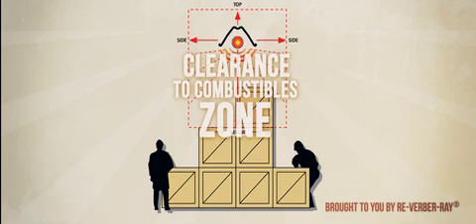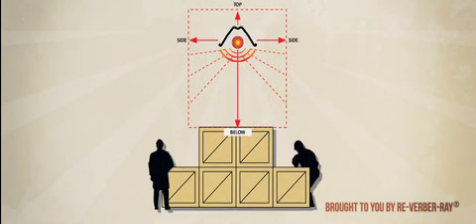Prior to finalizing heater placement, it's important to ensure that all clearance-to-combustibles distances will be maintained at all times, paying particular attention to storage areas, overhead doors, and car lift areas.